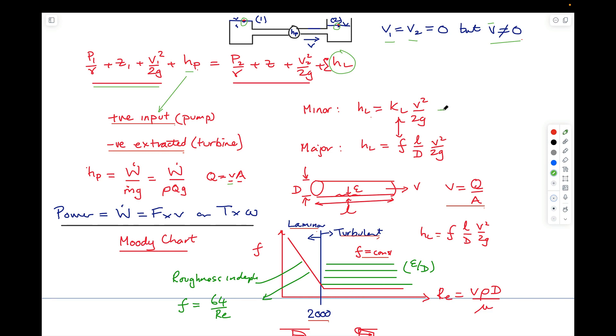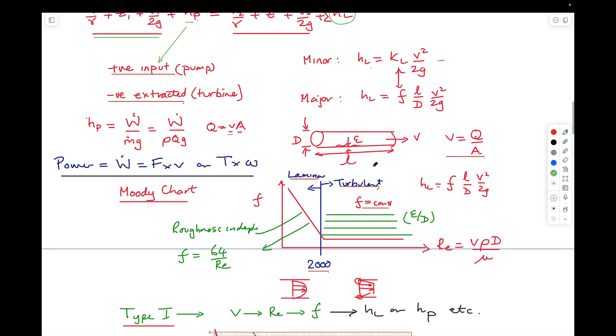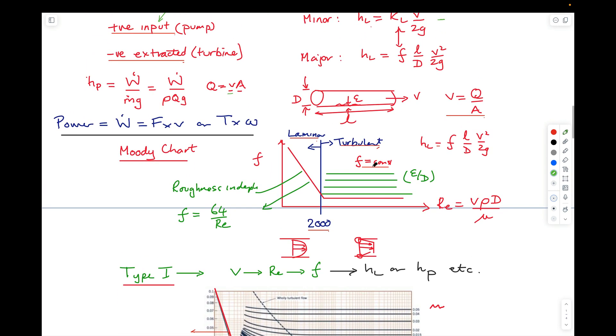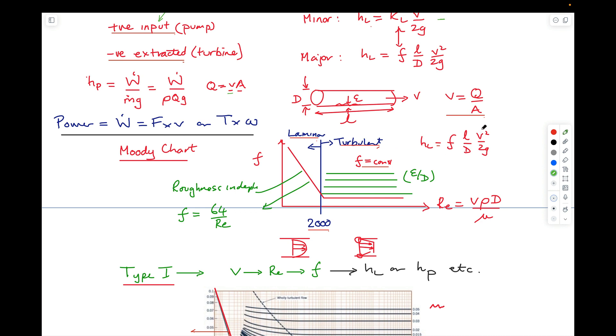For this test, you only need to be able to use the single loss equation. Pipes are defined in terms of diameter, length, roughness, and velocity. If you know the volumetric flow rate, calculate velocity from flow rate divided by area. Head loss scales with the length of the pipe — if the pipe is twice as long, the head loss doubles for a given flow velocity and appropriate friction factor, which is representative of the Reynolds number in the system.